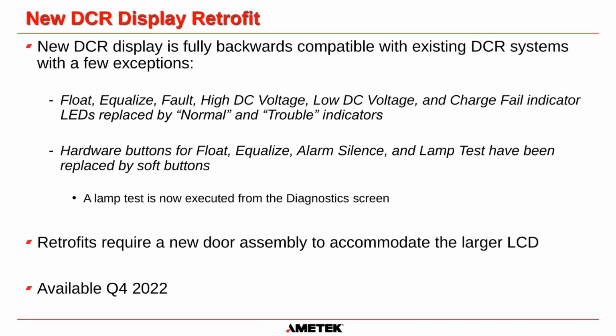The indicator LEDs on the old board were float, equalize, fault, high DC voltage, low DC voltage, and charge fail. Those are all replaced by two indicators — we either have normal or trouble. You can still see the status of all of those on the screen, but we don't have individual LEDs for them anymore, and the same goes for those hardware buttons.